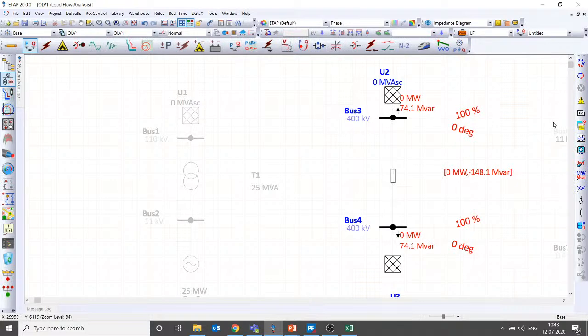If you have modeled your system with a multiple slack bus because the state is connected with many other states, and that bus is to be referred as a slack bus, then you need to give an appropriate voltage and angle in order to match the real and reactive power flow. So yes, the software allows you to model multiple slack buses. For all the slack buses, you can give voltage and angle. If you take all the bus voltage as 100% or 1 per unit and angle as 0, that may not solve your purpose. That will not match the power flow in each and every branch of your particular state.